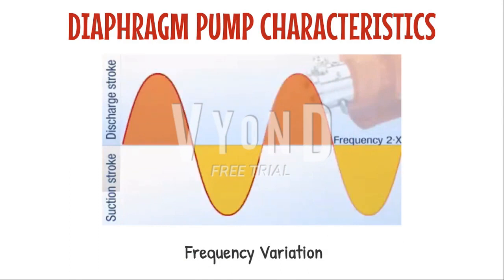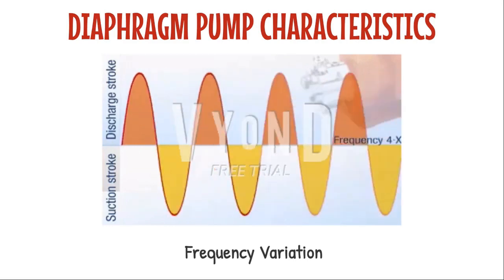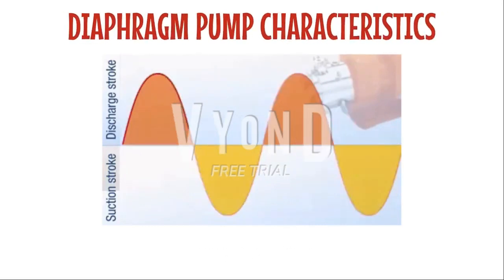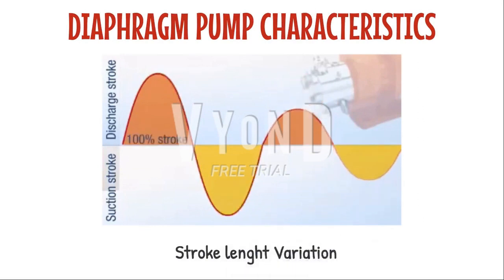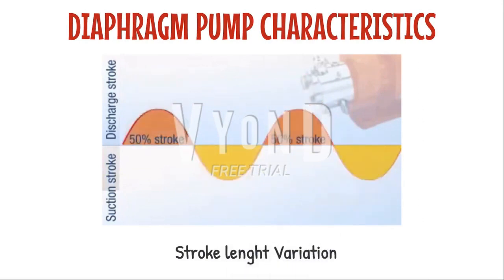The pump doesn't actually provide fluid for half of each shaft revolution. Increasing the motor speed increases the frequency of injection, and a high frequency is used for situations where good mixing is required. By adjusting the stroke length, precise flow control is also possible. By measuring flow at two stroke settings, graphing both locations, and drawing a straight line across them, other flow rates versus stroke may be predicted with accuracy.